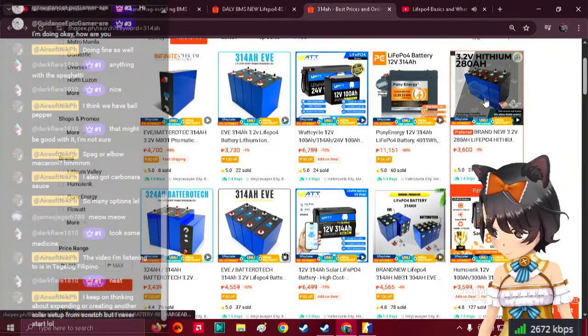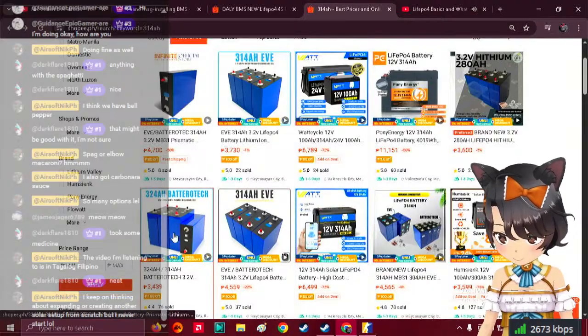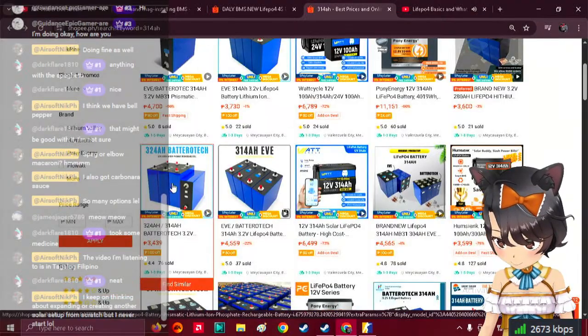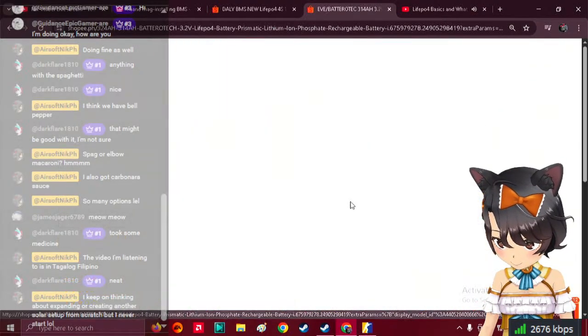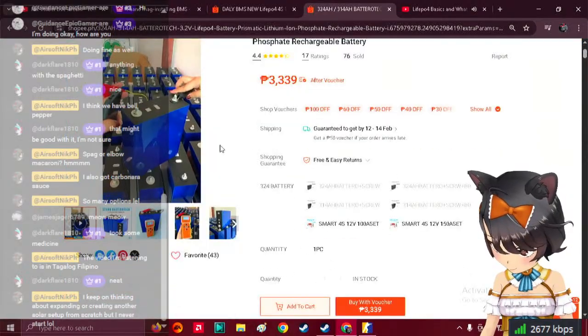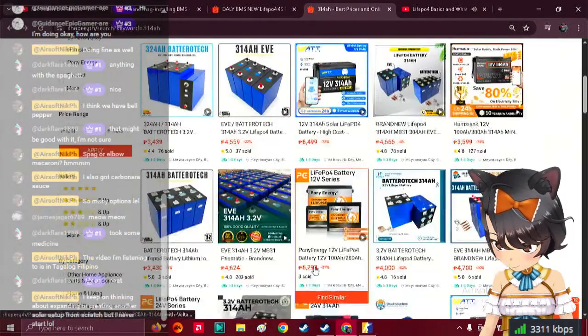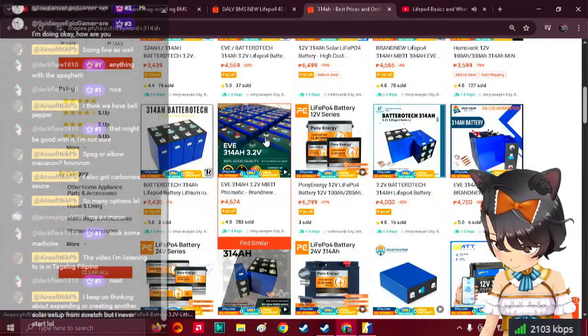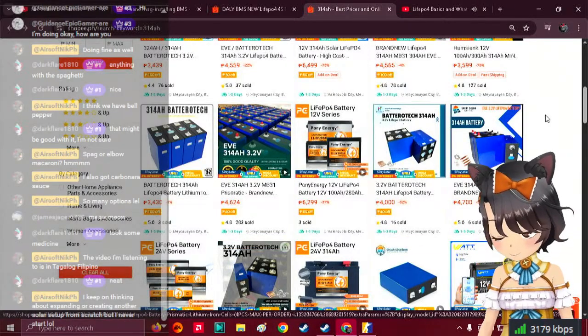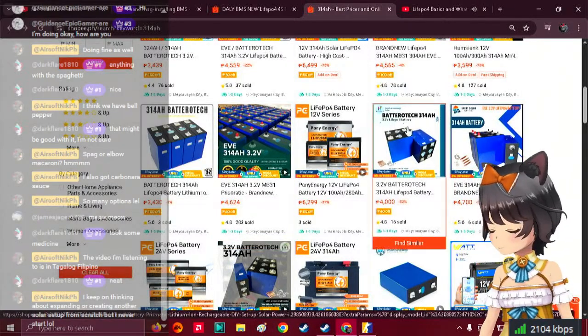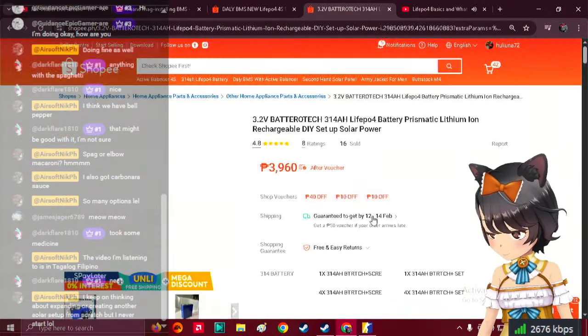Discharging is a little different—you can discharge below freezing, as low as negative 31 degrees Fahrenheit or negative 35 degrees Celsius, and it depends on the manufacturer; they might give slightly different ranges. I've seen different data sheets, so always check the data sheet for your batteries—that's a good point in general. They might have different temperature specs, but for lithium iron phosphate, never charge below freezing.